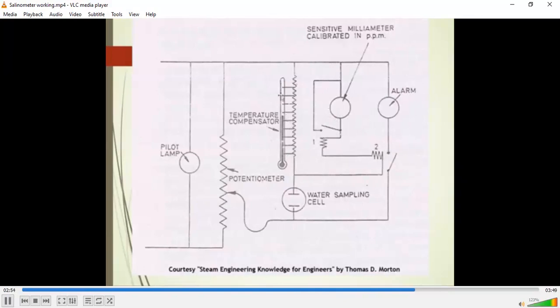There is also a temperature compensator. We know that water temperature increases conductivity, so temperature compensation is required. A temperature compensating device, basically a thermometer, is shunted across the meter, in parallel to it, to protect it. A temperature increase causes a rise in mercury level, cutting out resistance, which allows more current into the temperature compensator and less current to the ammeter, so it doesn't get damaged.